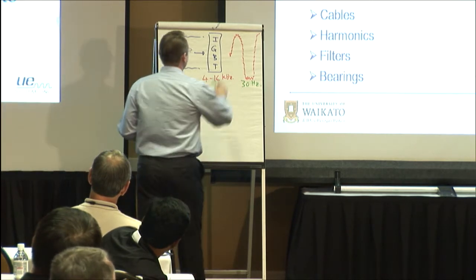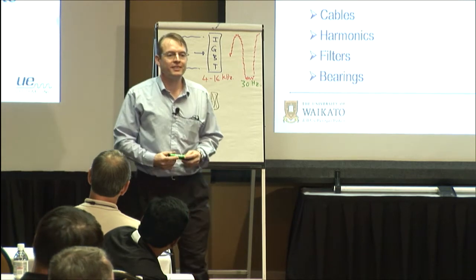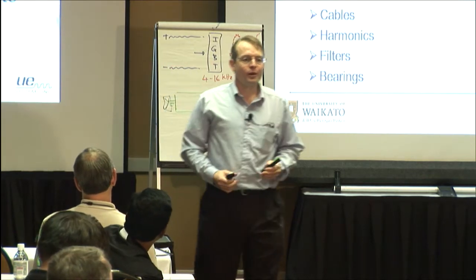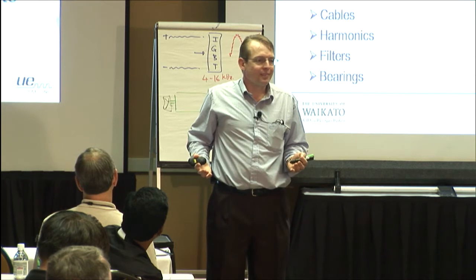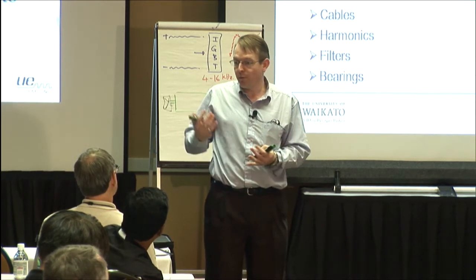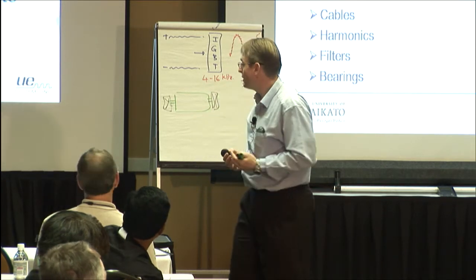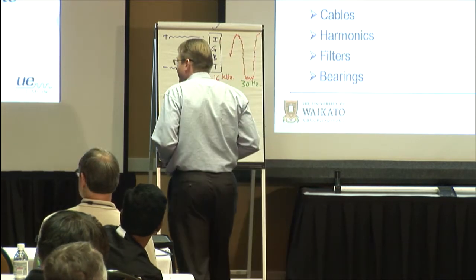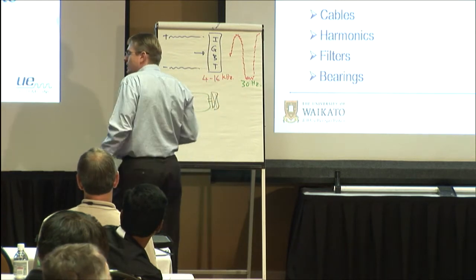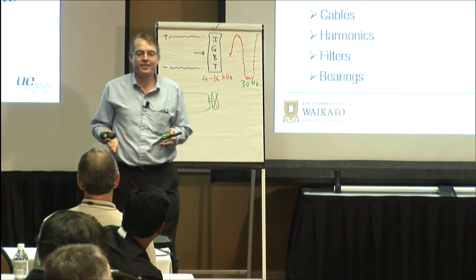Where do you think this excess energy from all these harmonics goes? Where does it build up? Yeah, on the rotor, right? So you've got a build up of voltage, a potential. Now the problem is that's always going to be looking for a path to ground.